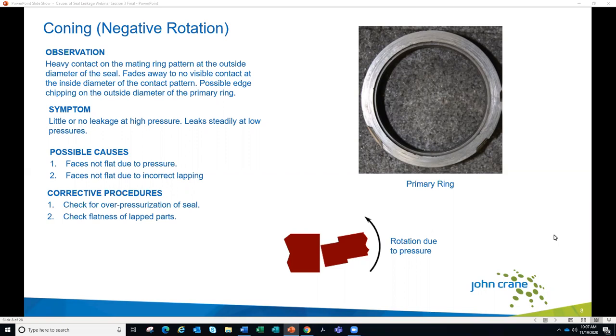If it's a result of over-pressurization, we'd want to make sure the seal is rated for the pressure of that service. If it's not, we might need to consider a change to the seal design, potentially a change to the materials we're using for the seal faces. If it's a flatness issue, that should be checked and caught during the seal assembly process, and we'll talk about how we make sure the seal faces are flat.